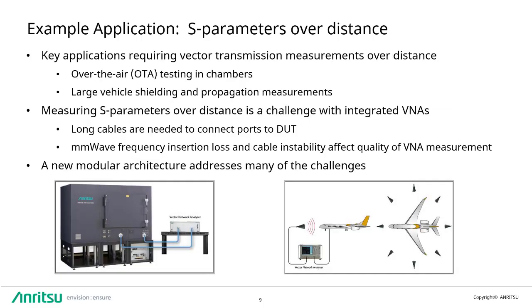Measuring S-parameters over distance presents unique challenges at millimeter wave frequencies that modular VNAs can help overcome. Connecting ports on an integrated VNA to antennas in over-the-air chambers or around large vehicles for shielding and propagation measurements requires long lengths of cable.